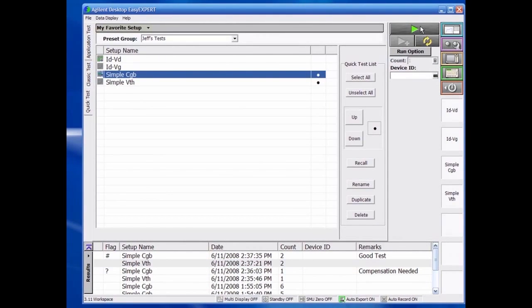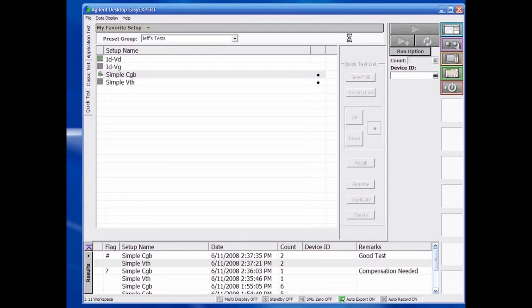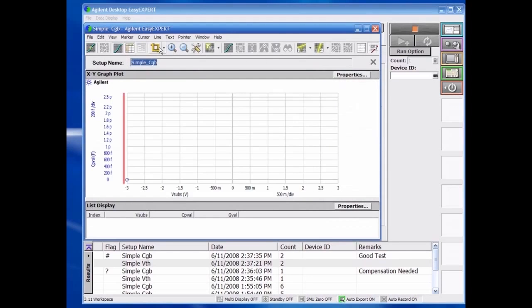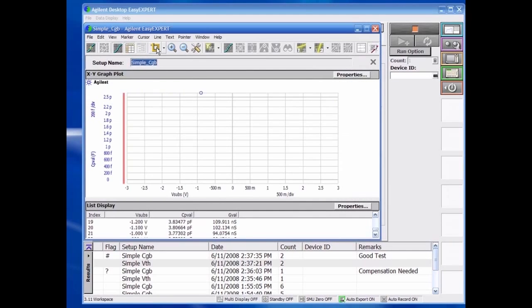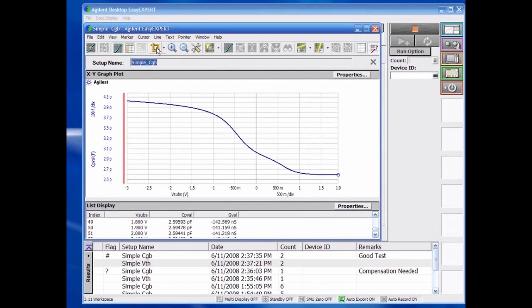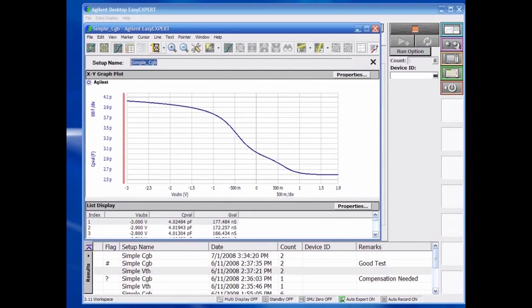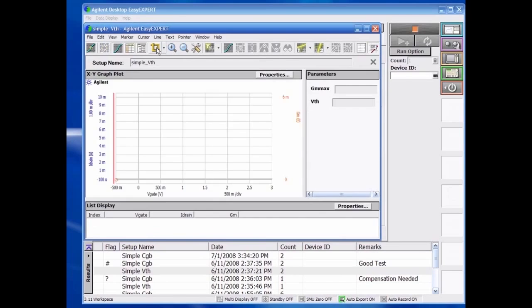Because the B1500 is network-ready, you can even choose a network drive as the destination folder, which allows you to use the test result at a separate desktop PC while the instrument is performing a test in the lab.